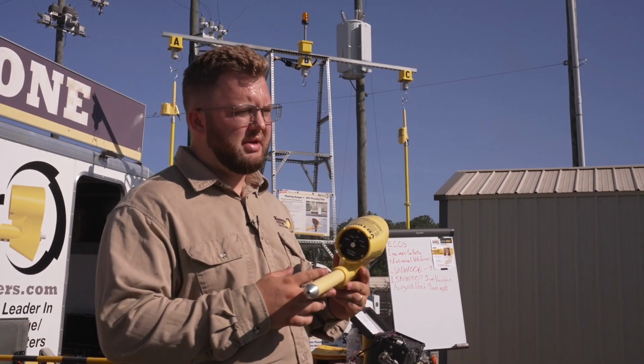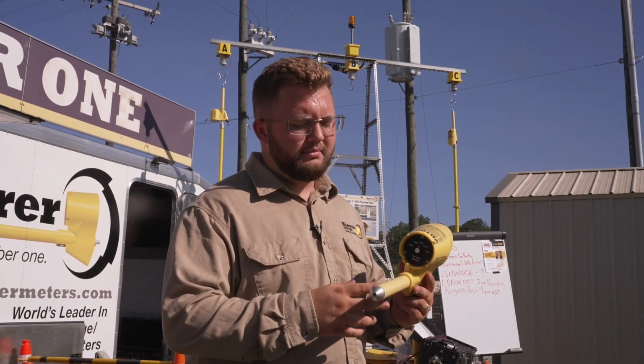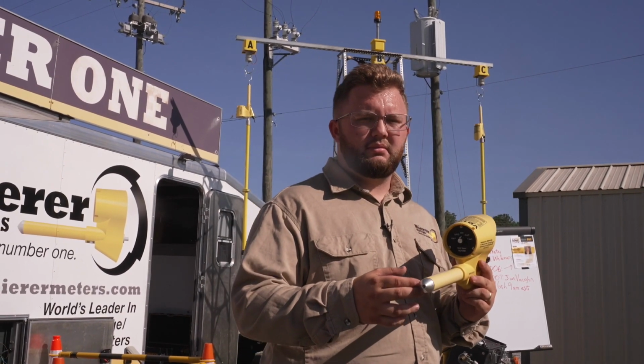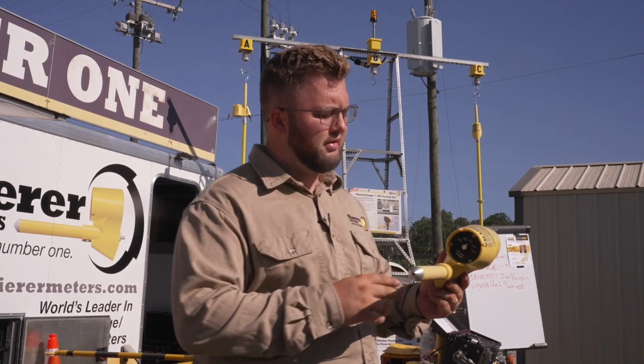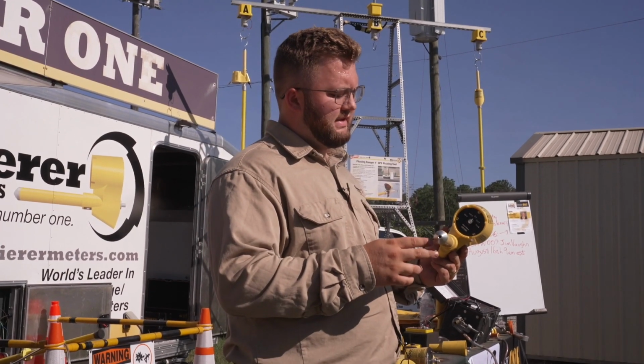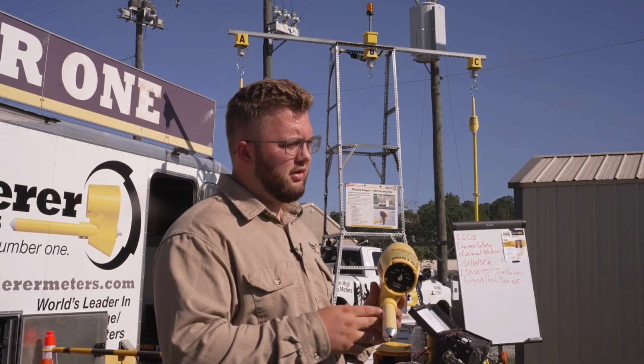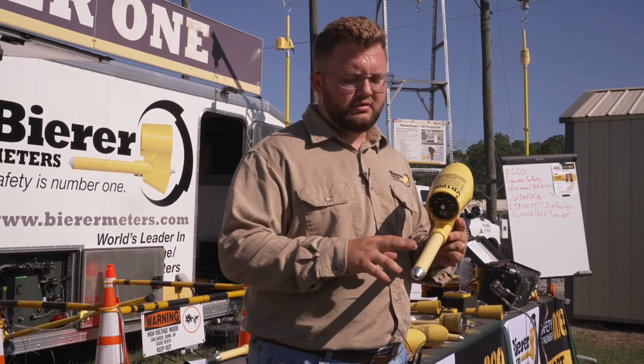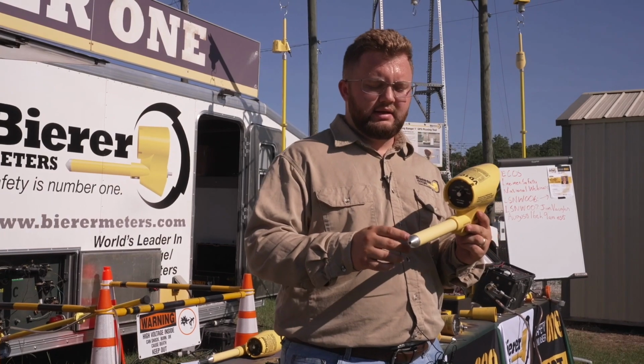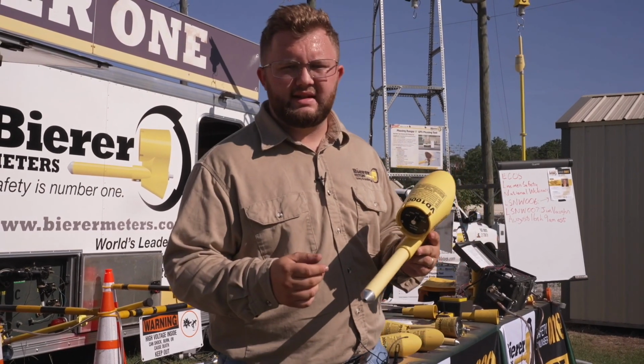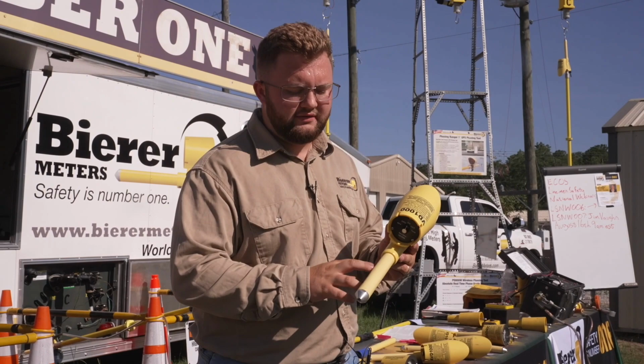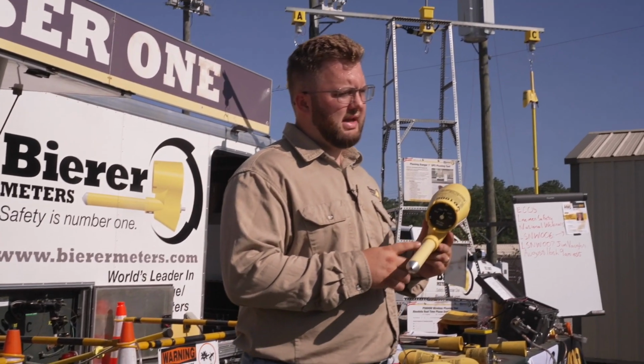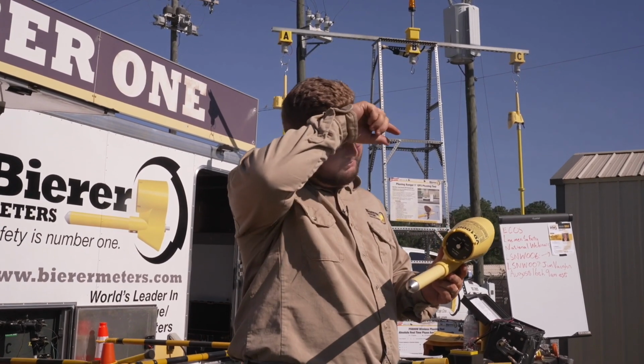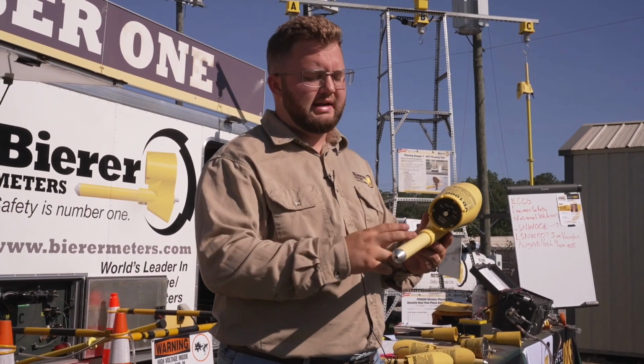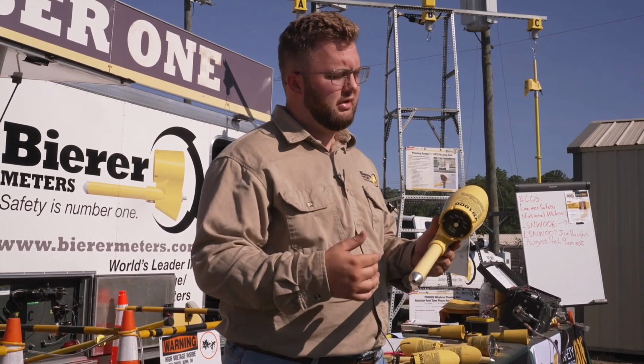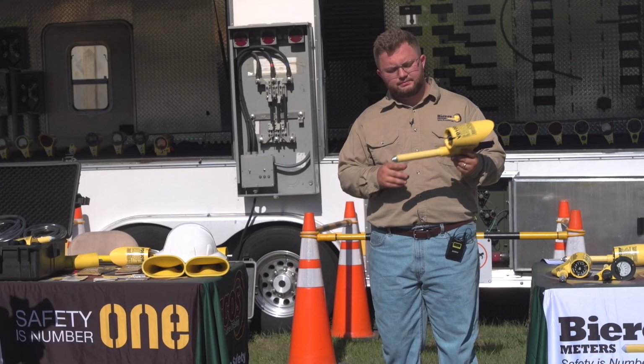That epoxy is going to keep out any type of water, dirt, grime, to limit an internal flash to those conductive components. So since this probe is insulated, you can't get any water, dirt, grime. What you're going to want to also do is keep the probe itself clean. How you would do that is just by using your regular hot stick wipe. You're going to wipe down the tool, keep it clean from any dirt, grease, grime, any type of calibration stickers, anything that could cause a potential track down the outside of this tool, same as you would your hot stick.